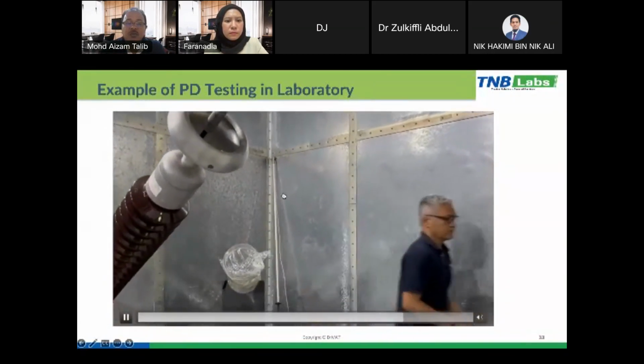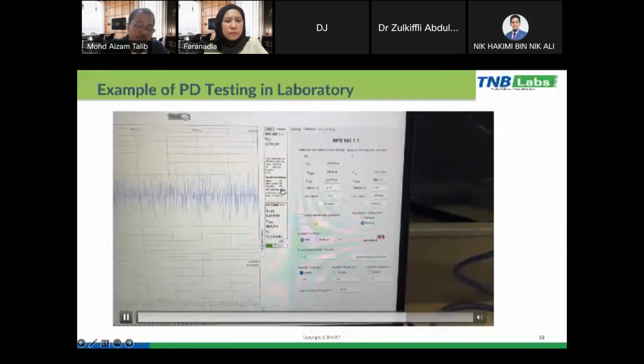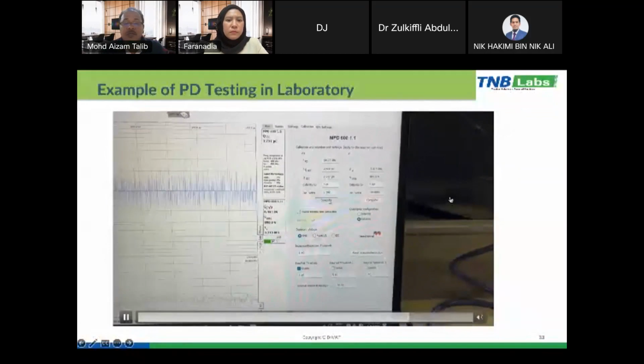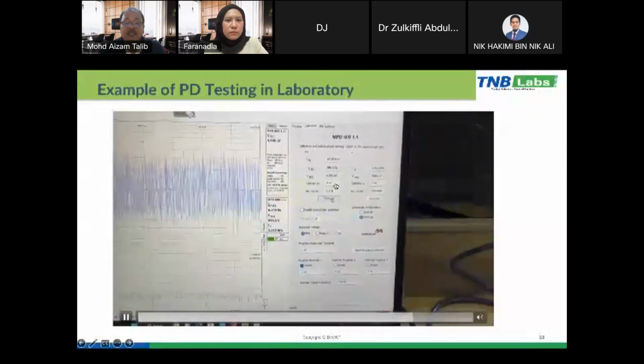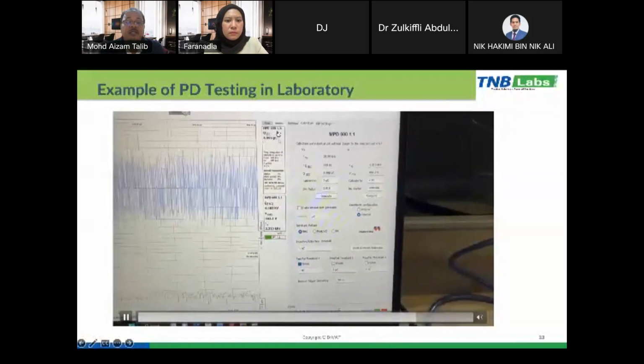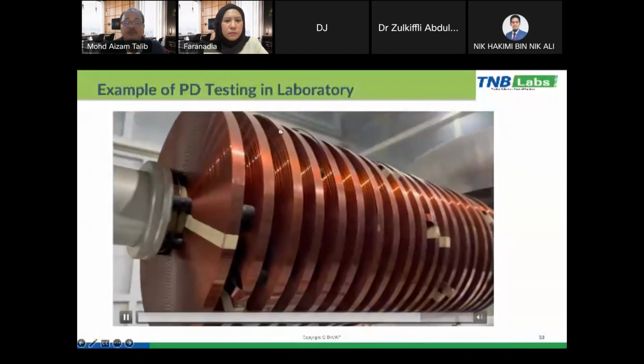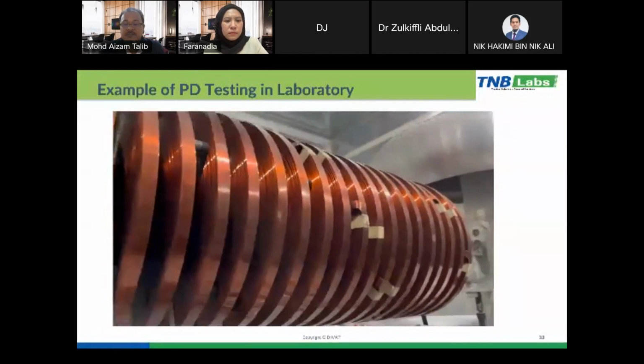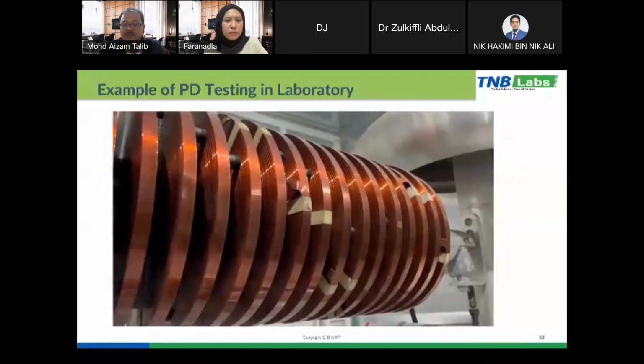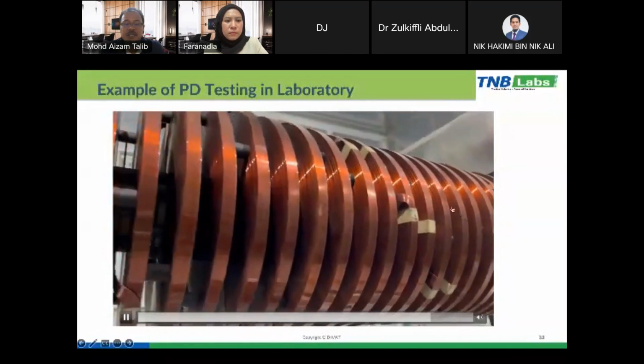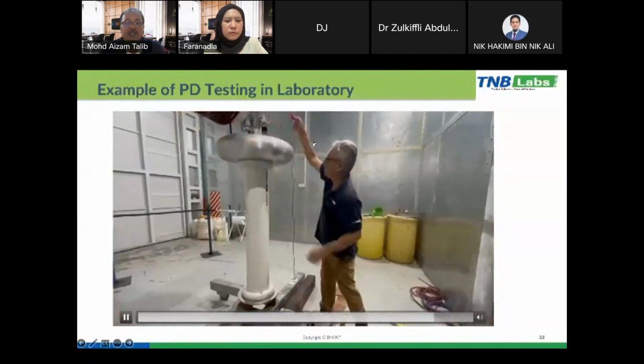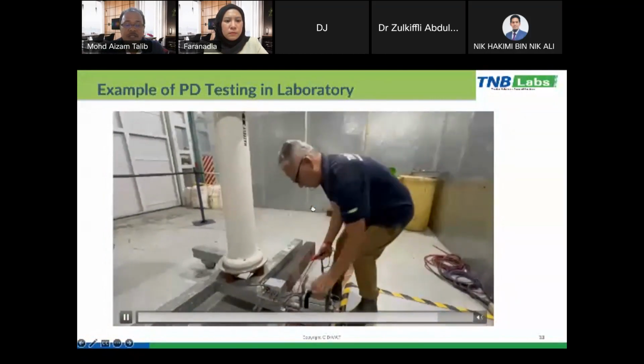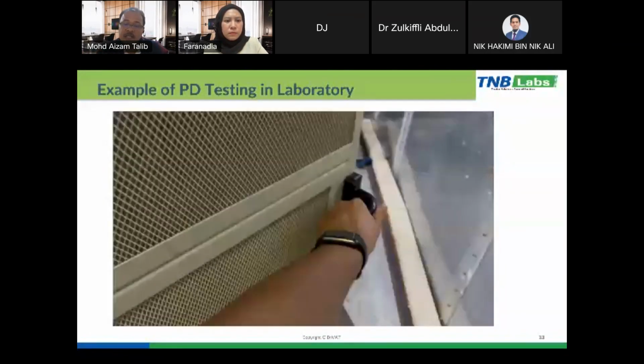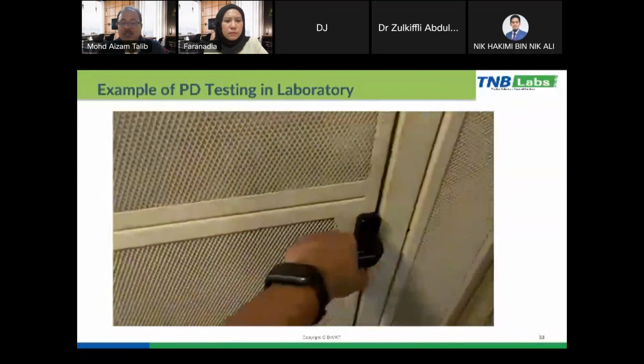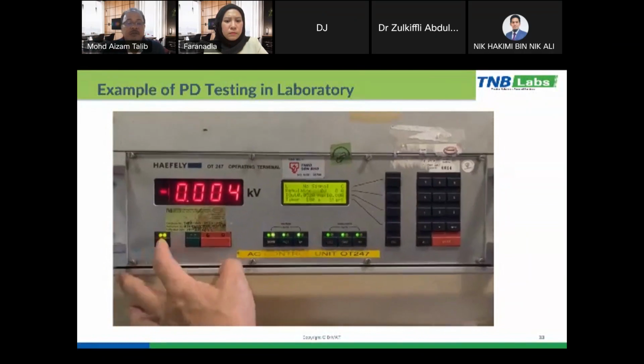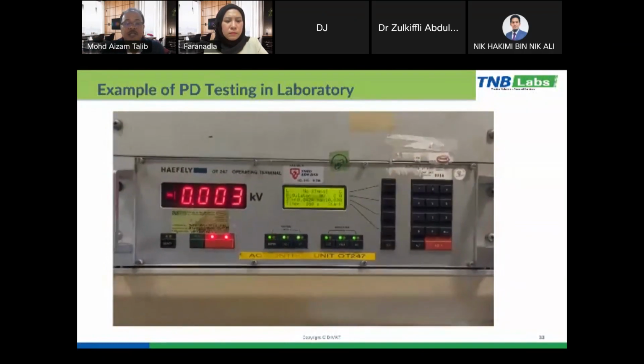So we need to remove the safety switch, the safety hooks. And then we ask the system to calibrate 5 picocoulomb, and then we see the system will measure 5 picocoulomb. Okay, this is our blocking impedance or HV filter. And then we remove the calibrator before we actually test the cable. And then we close the door, and then we increase the voltage.